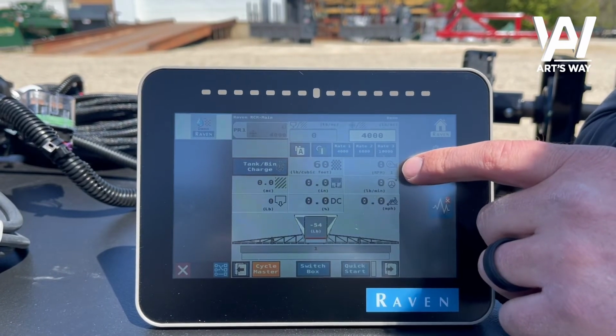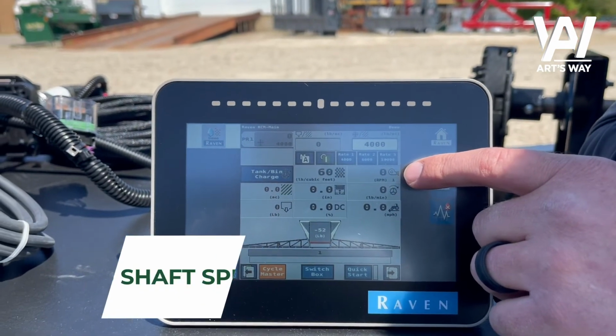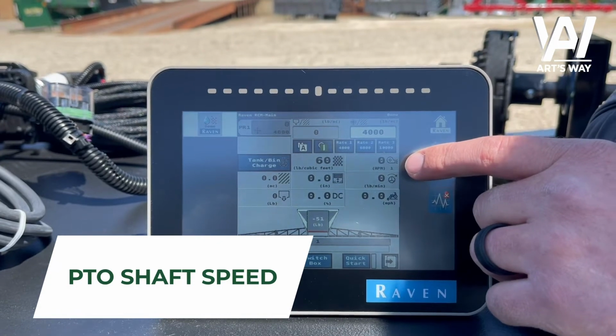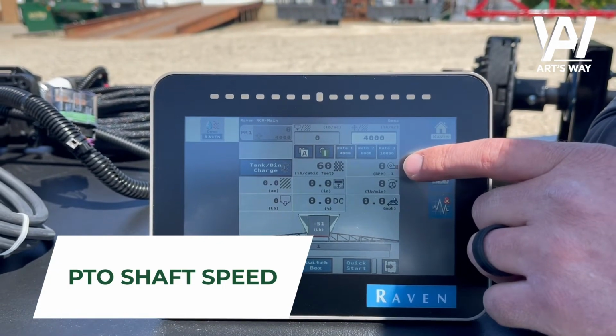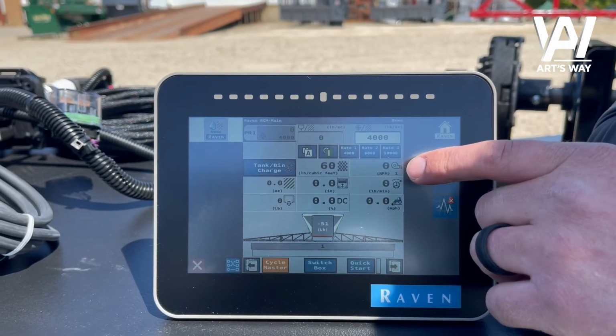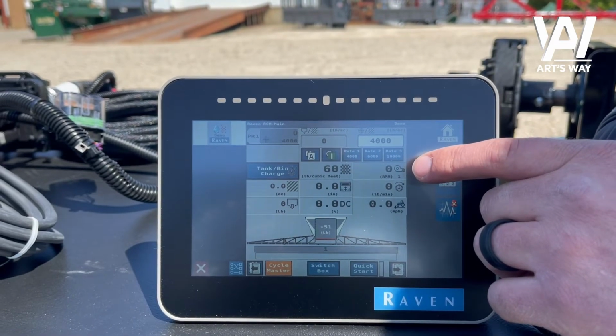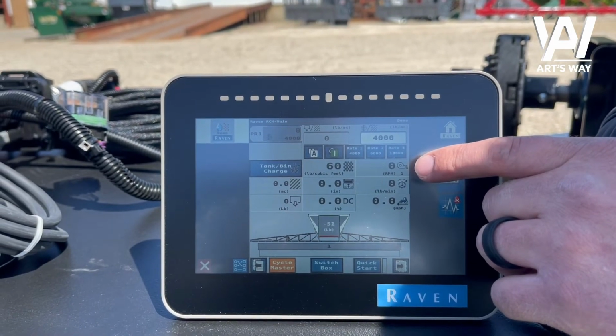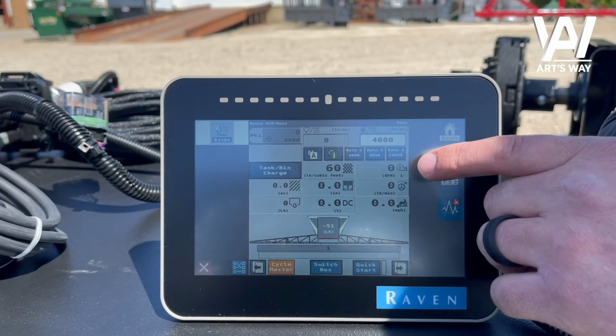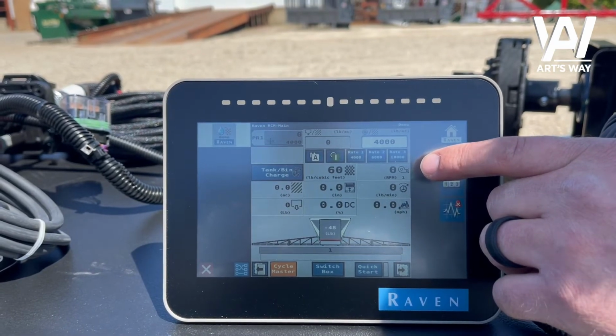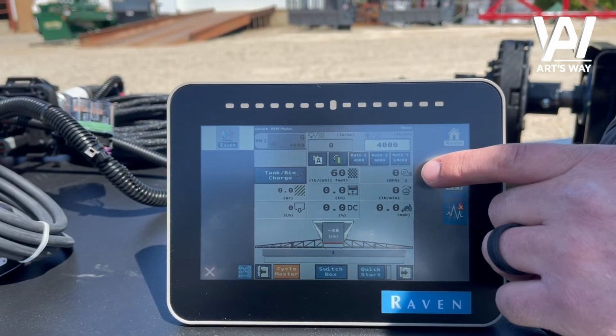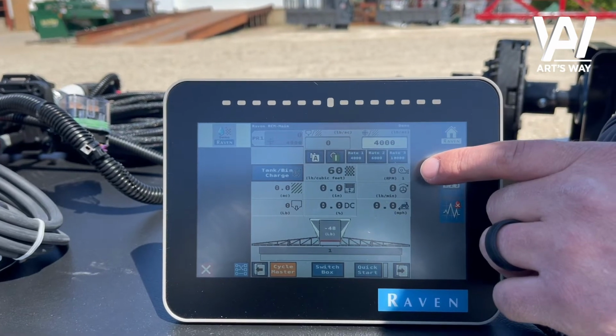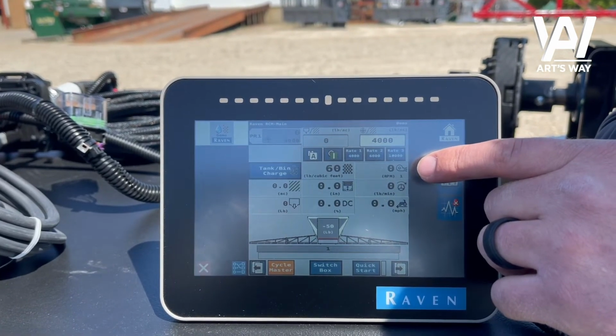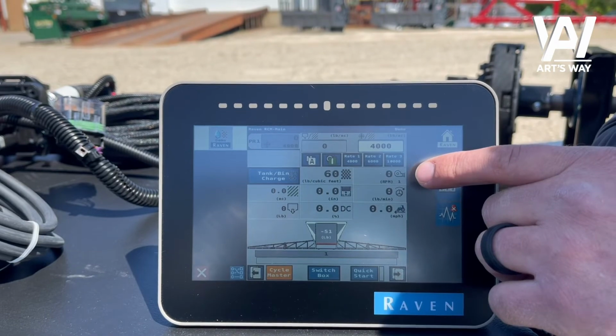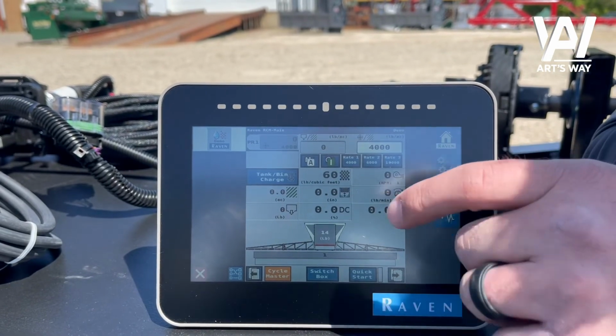The RPM 1 readout up here is where you get your PTO shaft speed. If you have a 0 speed there when the PTO is on, check the sensor, make sure that it's close enough to the target so that you can pick it up. With that assigned to product 1, we will not run the apron as long as we are not seeing any PTO RPM, so that's an important one.